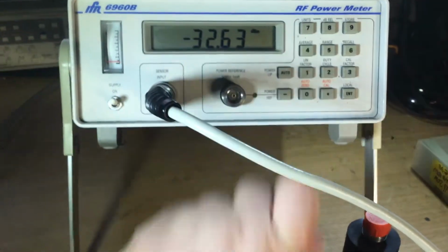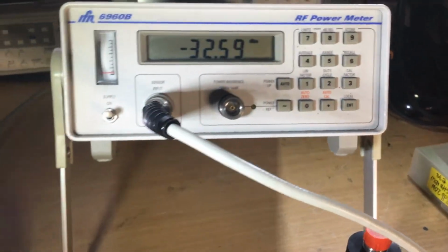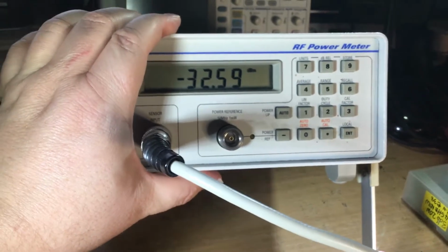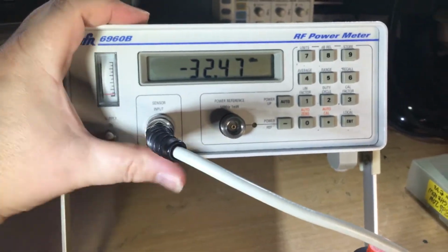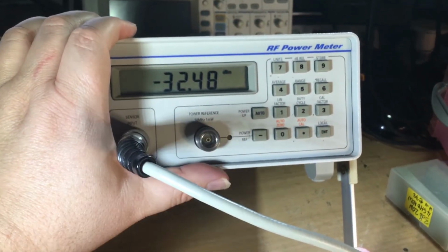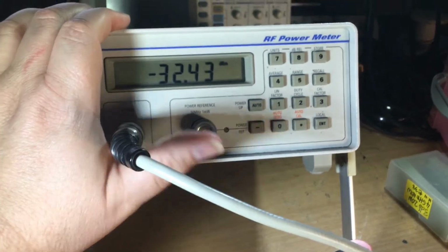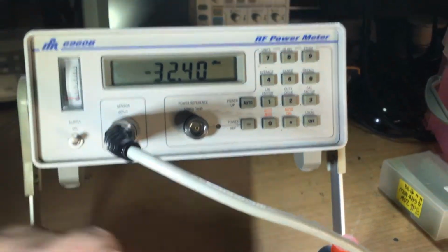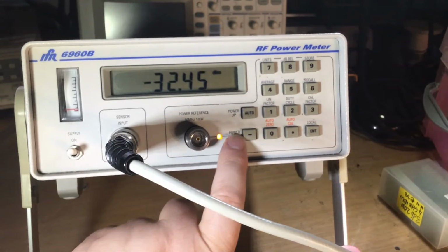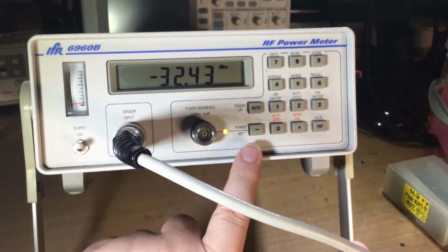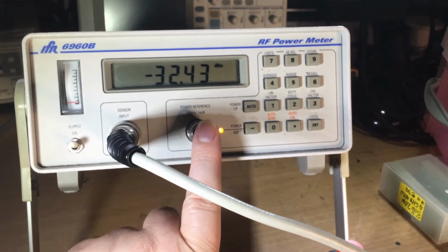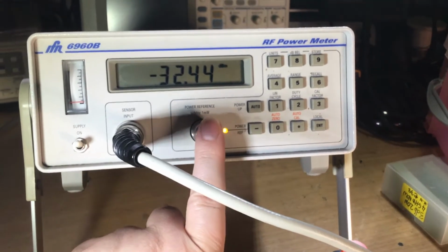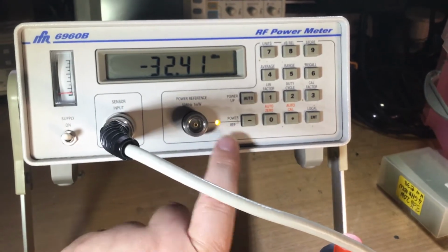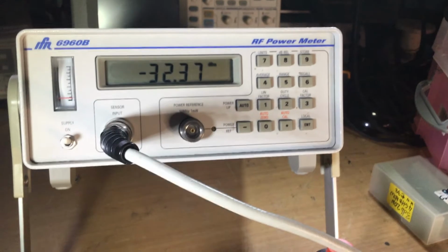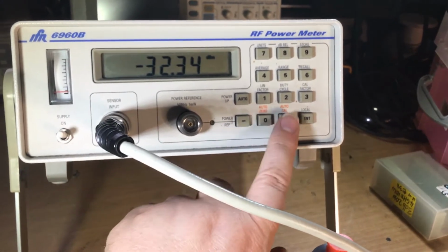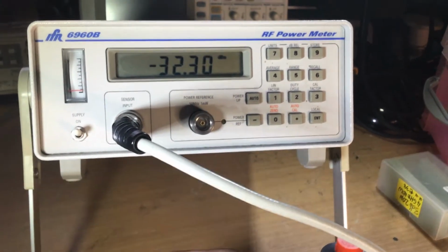So this is where this port is here, this N-type, which is not an input. Quite a lot of people who are inexperienced inadvertently and accidentally connect RF in there and blow the unit up. This is an output, not an input, and so we can set a signal up to come out of here, which the sensor uses then to calibrate itself. It's a 1 milliwatt or 0 dBm level at 50 megahertz, and that's what it uses. We've got auto cal features, auto 0 here, which we're going to use in a moment.